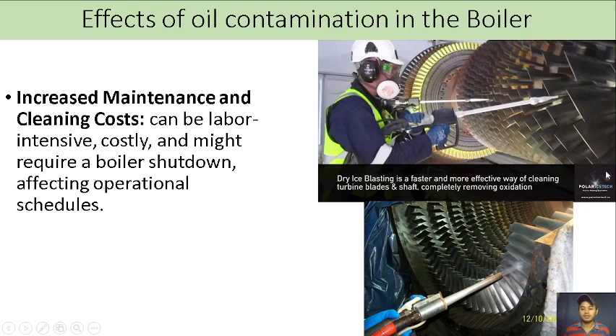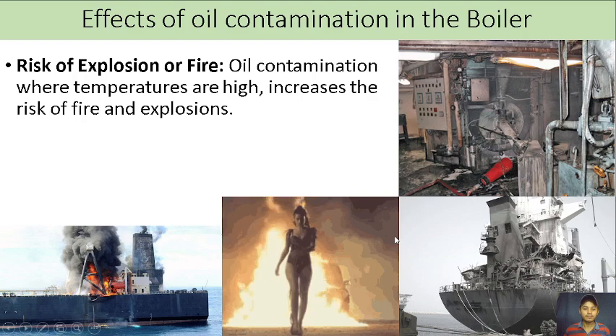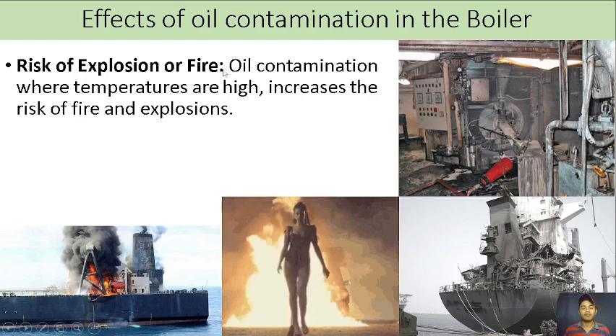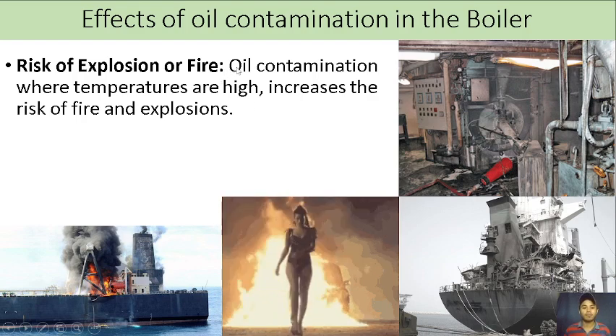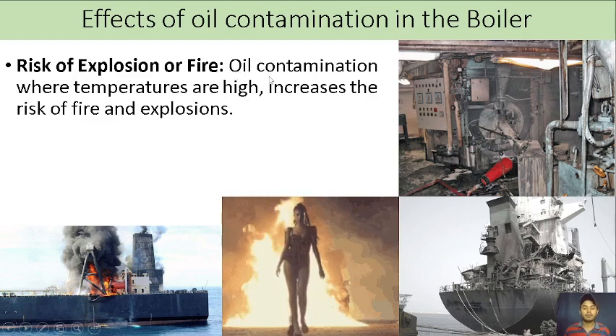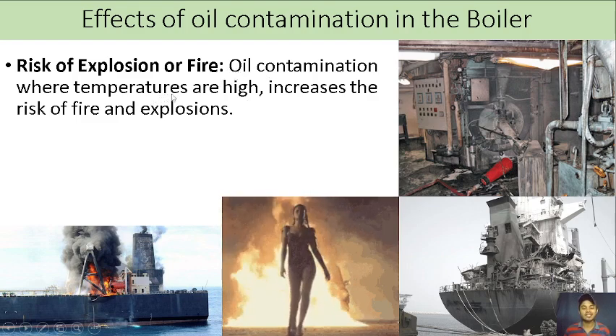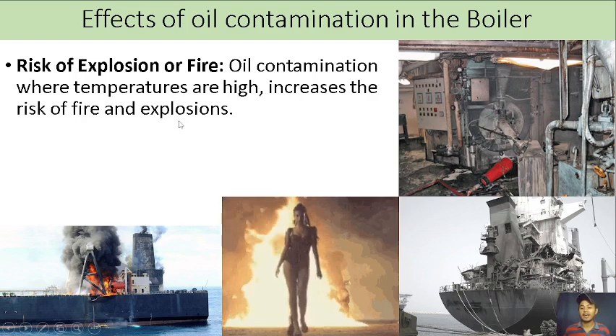In this picture, we can see dry ice blasting is a faster and more effective way of cleaning turbine blades and shaft, completely removing oxidation. You will have to do this if there is oil contamination in your turbine. Another effect of oil contamination is the risk of explosion or fire. Oil contamination where temperatures are high increases the risk of fire and explosions.